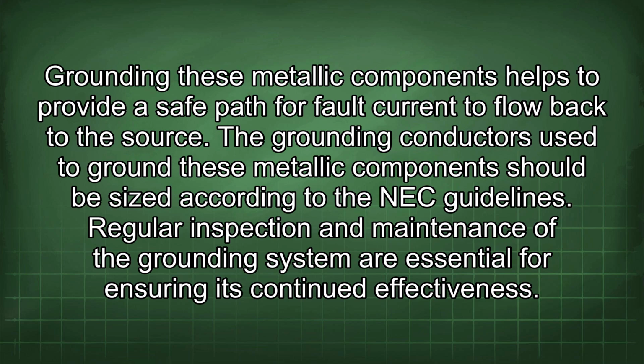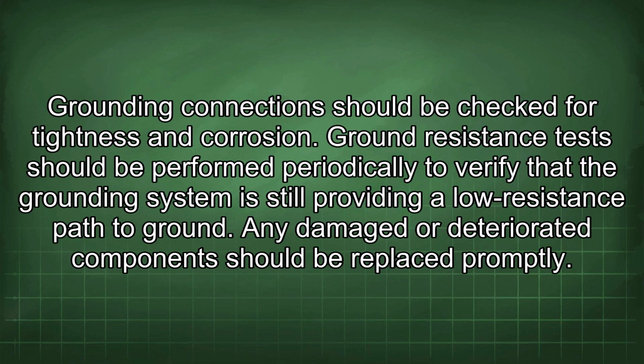Regular inspection and maintenance of the grounding system are essential for ensuring its continued effectiveness. Grounding connections should be checked for tightness and corrosion. Ground resistance tests should be performed periodically to verify that the grounding system is still providing a low resistance path to ground. Any damaged or deteriorated component should be replaced promptly.